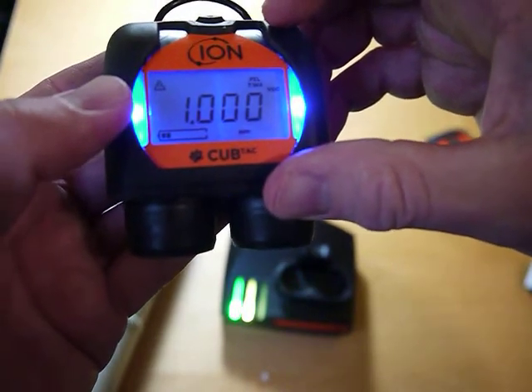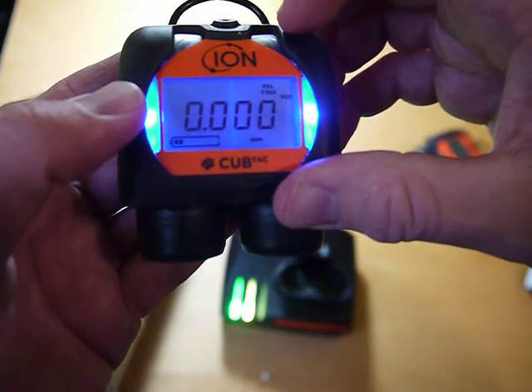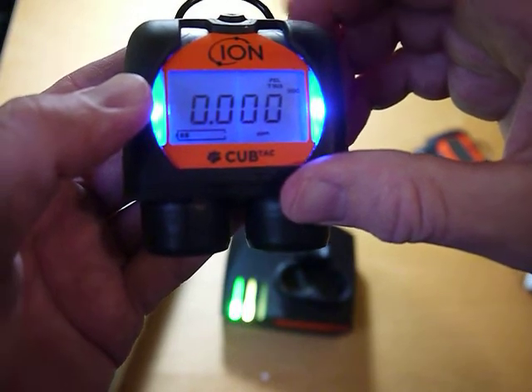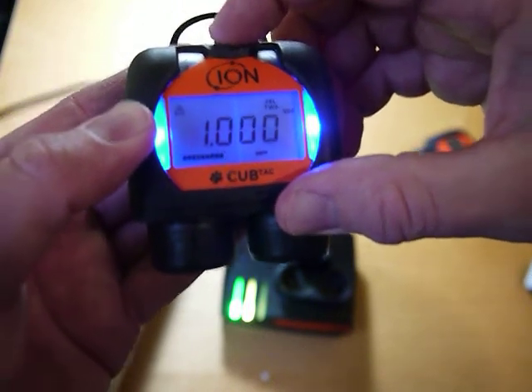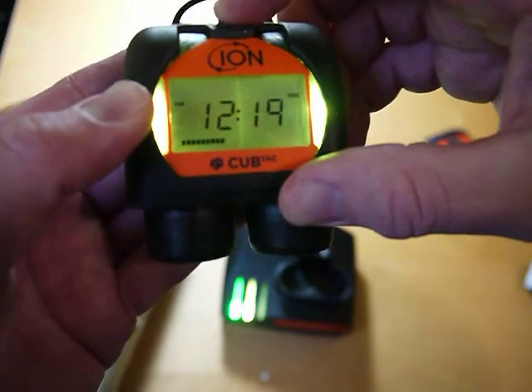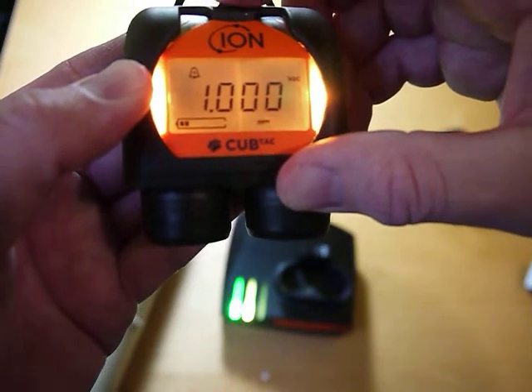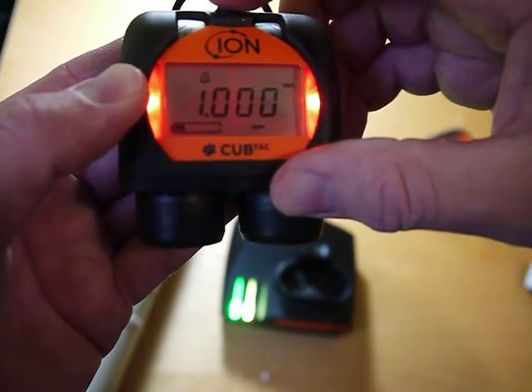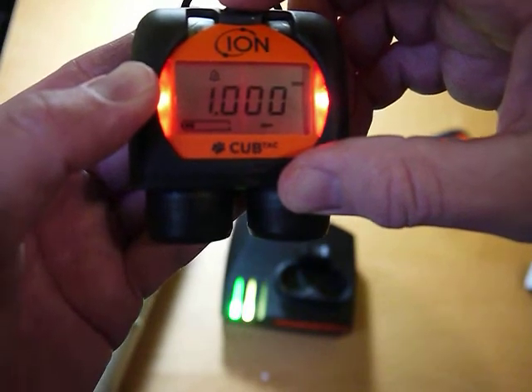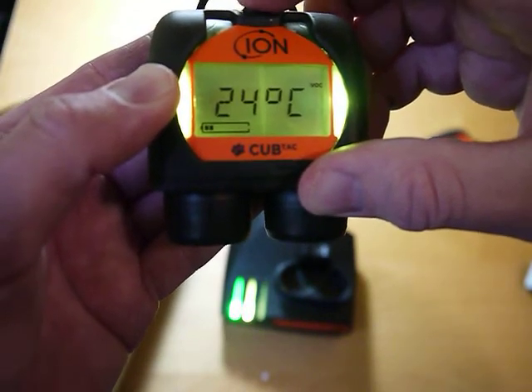Now it's showing me the TWA alarm at 1 ppm and the calculated value so far, which is still 0. The time, the low alarm, the high alarm, I set them both to 1 because this is more for benzene application. The temperature.